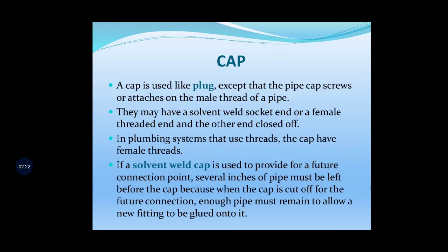In plumbing systems that use threads, the cap has female threads. If a solvent weld cap is used to provide for a future connection point, several inches of pipe must be left before the cap, because when the cap is cut off for the future connection, enough pipe must remain to allow new fittings to be glued onto it.